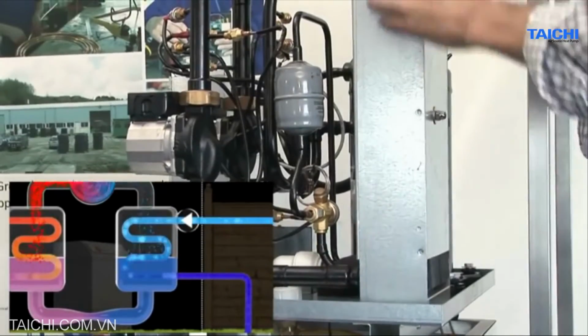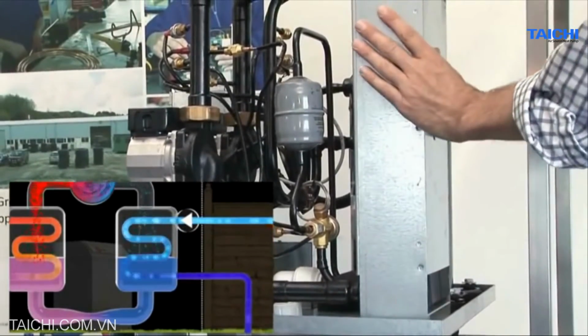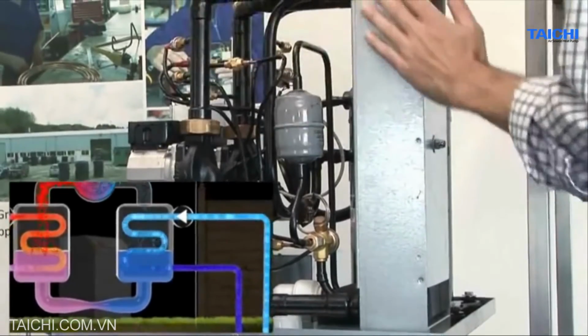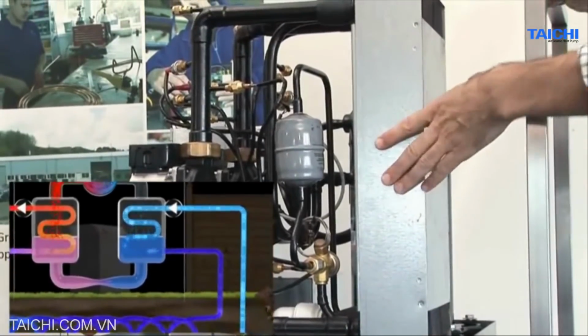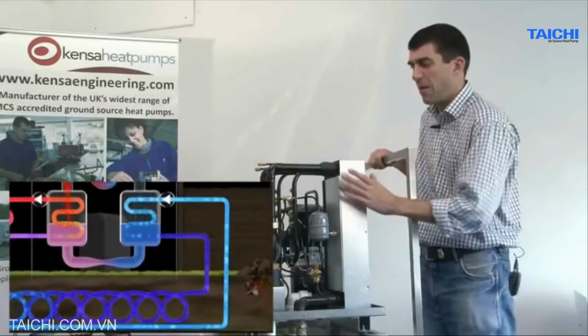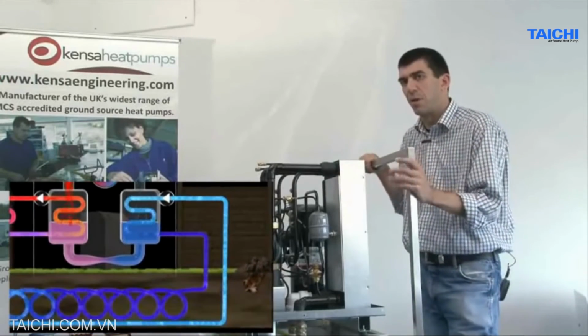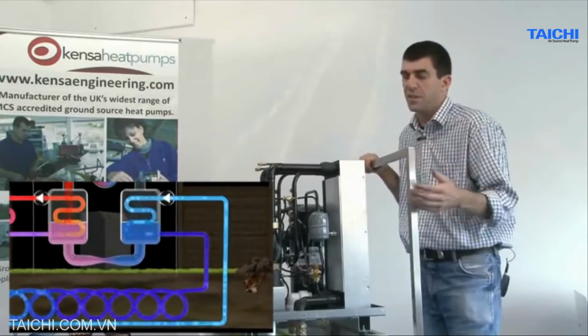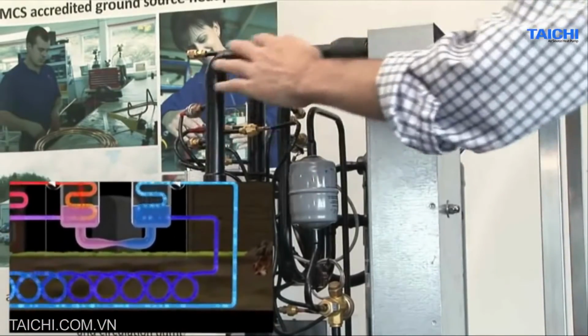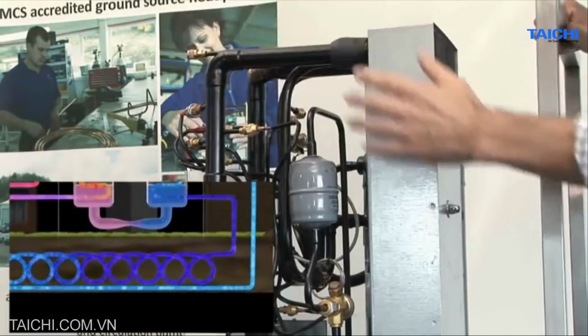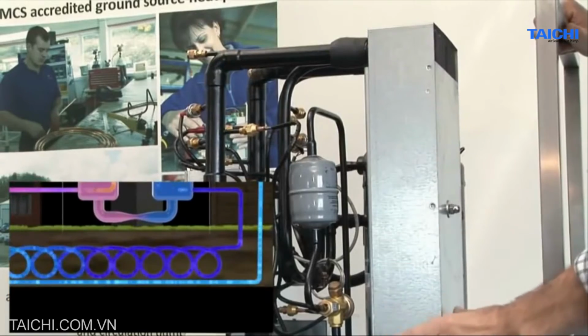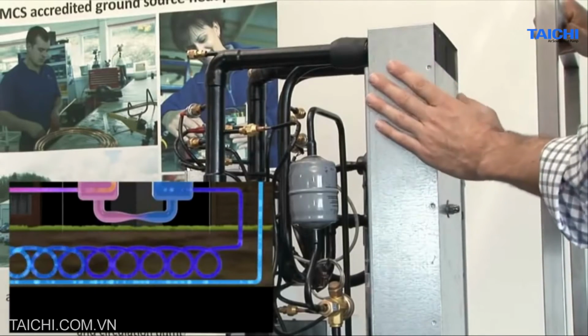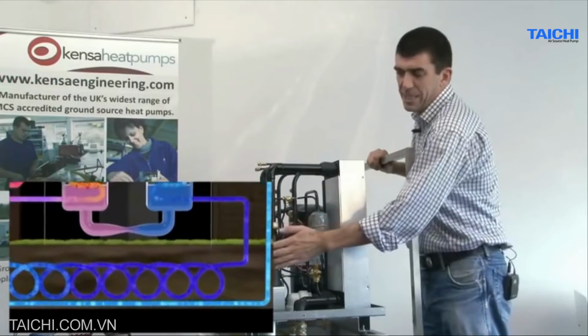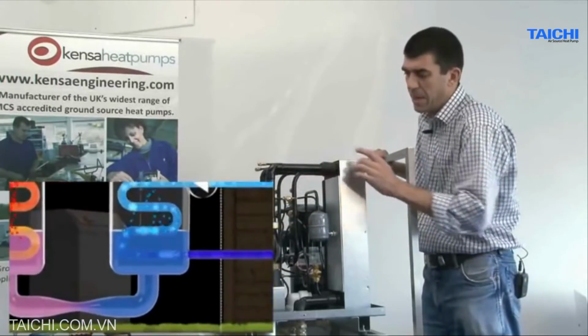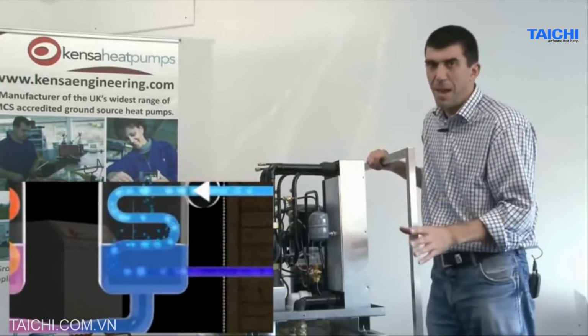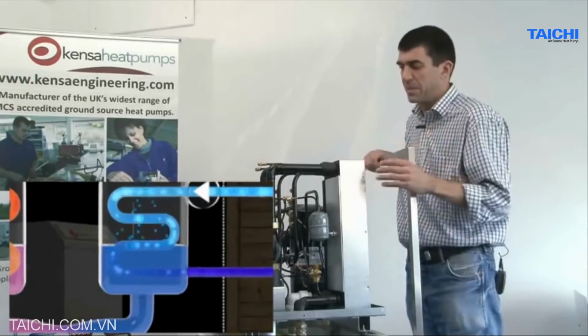We give it the required thermal energy by passing it through the heat exchanger of the ground side water. It's not very warm, but it's warm enough. This refrigerant has a boiling point of about -30 Celsius. Typically our ground temperature is +5 Celsius or somewhere around there. So it's plenty warm enough to boil the refrigerant back into a vapor. The water probably enters from the ground array at 5 degrees C, and when it comes to leave, it's probably down to about 0 degrees C. They're quite normal operating parameters.